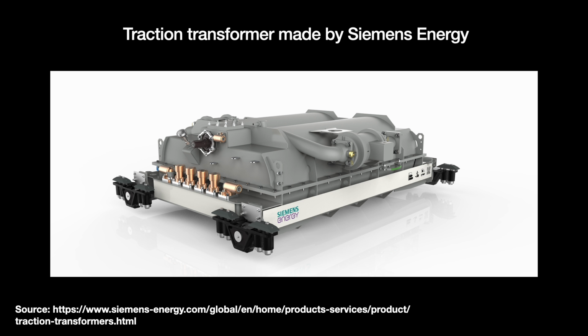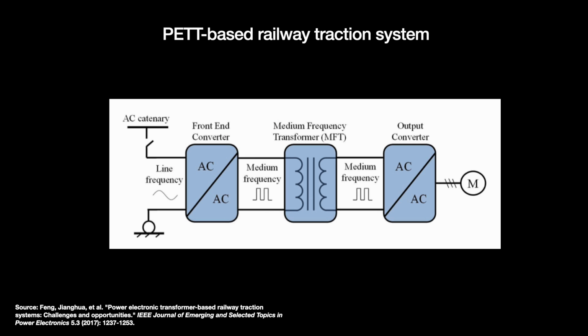The PET that ABB presented was a 3-stage device. The first stage takes an AC input from the line and raises the frequency using silicon IGBTs, which stand for insulated gate bipolar transistors, and became commercially available in the 1980s. The second stage is a medium frequency transformer that steps down the voltage. Then finally, the third stage is a converter that can produce power that feeds into the train's traction drive.